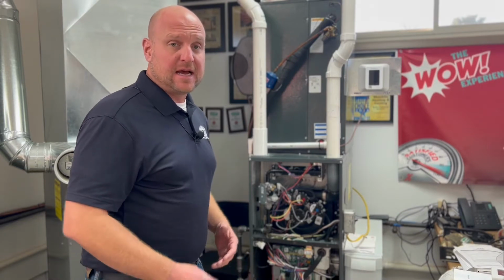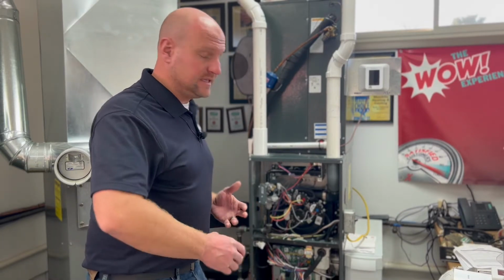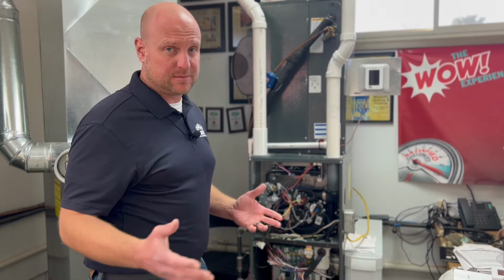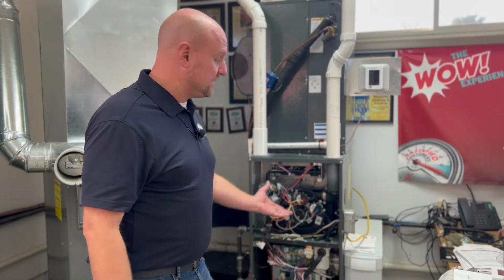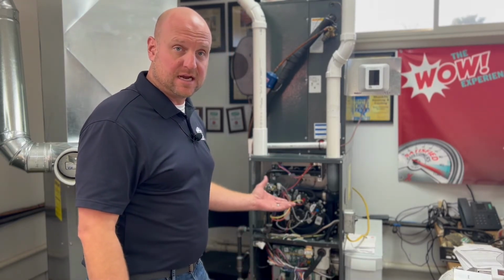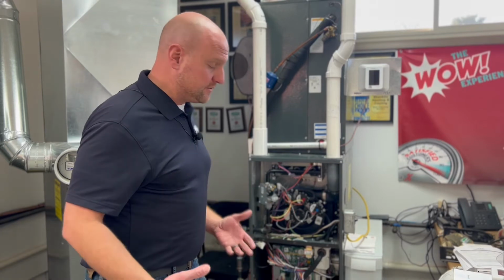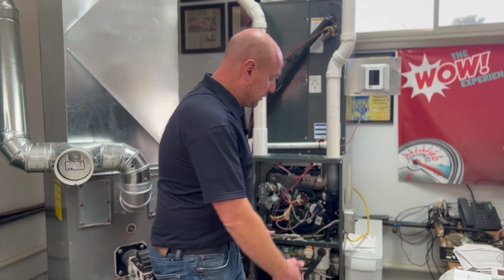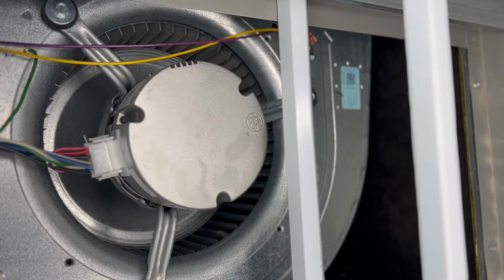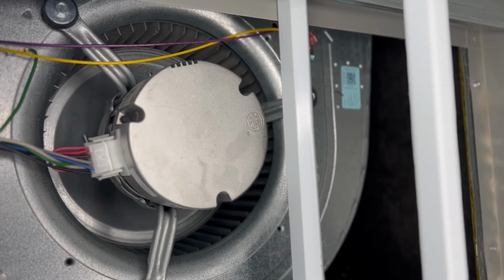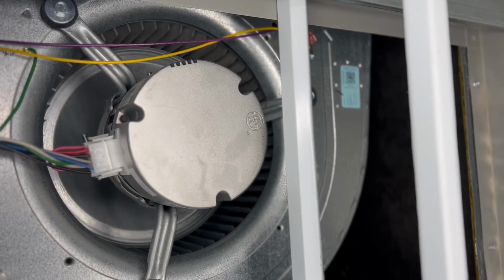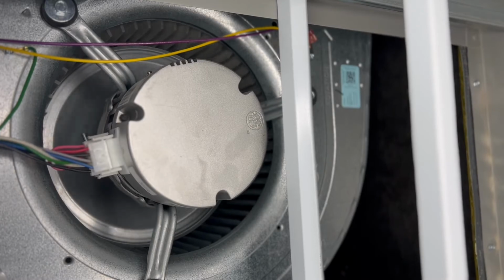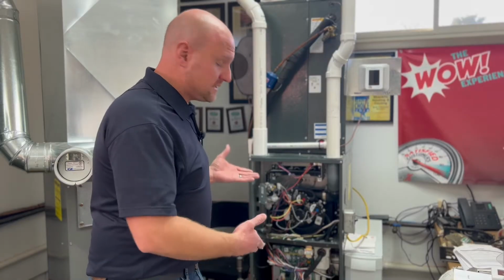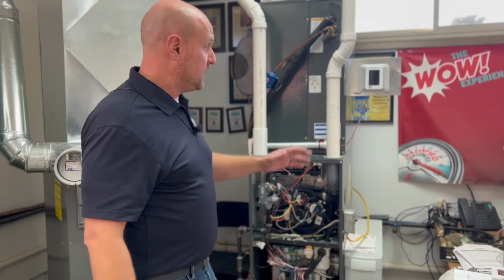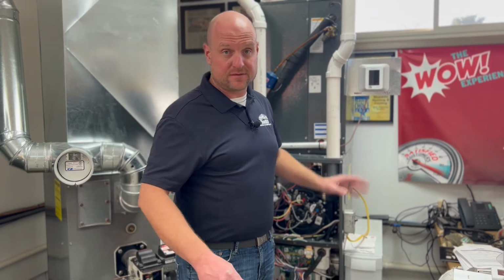After this, the circuit board is going to go into a timer, allowing 30 to 40 seconds, depending on the model, to give the heat exchanger time to heat up before it starts moving air. At the end of this timer, the blower motor in the blower compartment is going to turn on and start blowing air across the heat exchanger, cooling it down and distributing the heat throughout the ductwork. This process is going to continue until the thermostat says, I'm satisfied.